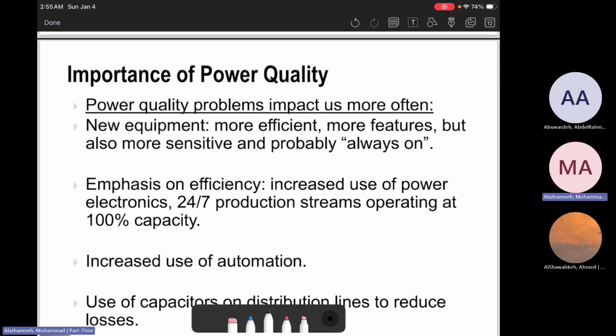The other thing is the shunt capacitors in the distribution line. Those shunt capacitors are used to reduce the losses, to improve the voltages, and to supply reactive power. But the switching transient, when you turn these switching capacitors on and off, will make a big, huge transient. That transient can cause poor power quality. It can cause a significant voltage drop or a significant voltage rise that can impact the performance of the power system. And it also impacts the end customers.